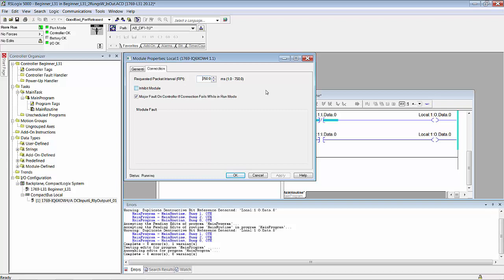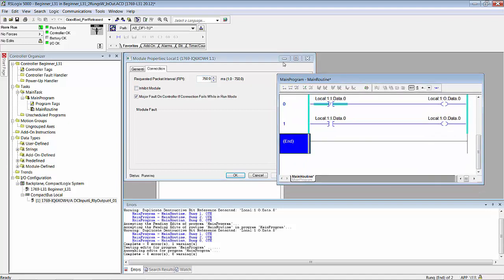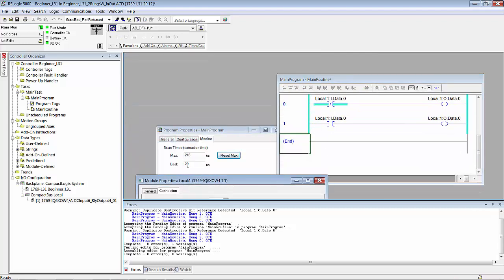In the manual, roughly page 111 or so, I have a diagram that shows this relationship between the RPI and the scan time. And it states that every 10 microseconds, the logic tells the bit memory to change state from on to off or off to on. So if you're executing these two rungs of logic here, every 10 microseconds or so, this logic is telling that bit that it's in a different state. At 20 milliseconds, the I/O task updates the output module with the current state of that bit.